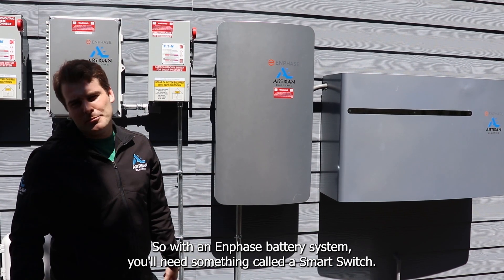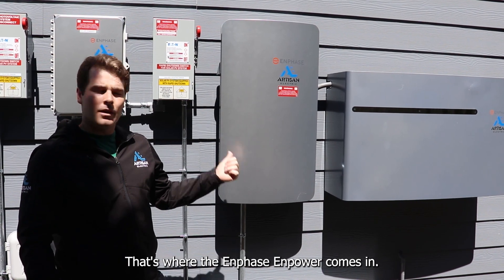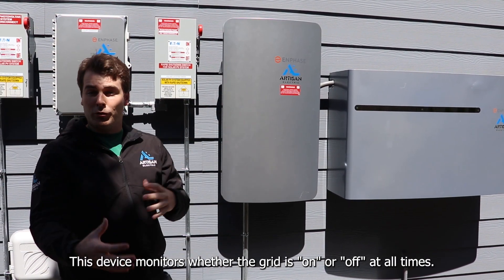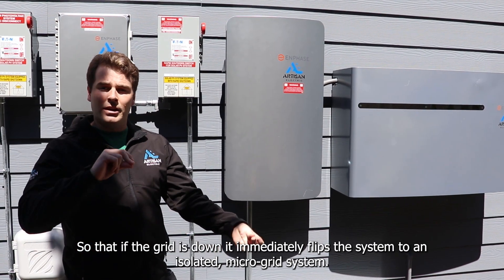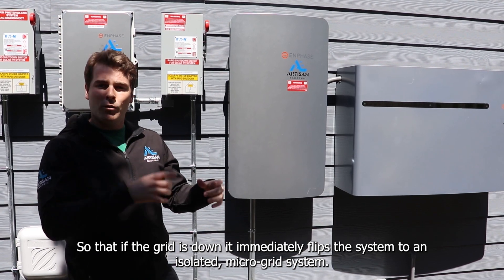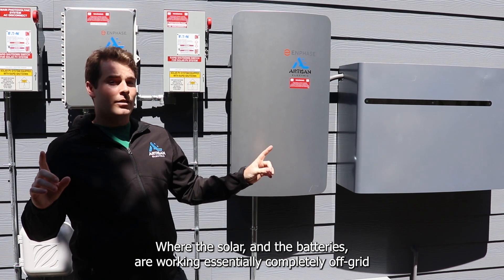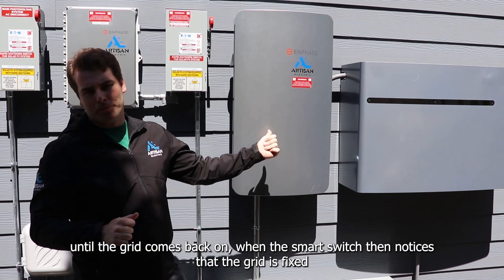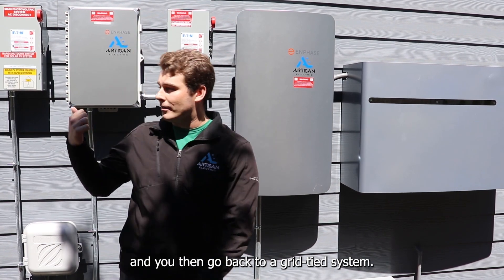With an Enphase battery system you'll need something called the smart switch — that's where the Enphase Enpower comes in. This device monitors whether the grid is on or off at all times, so that if the grid is down it immediately flips the system to an isolated microgrid system where the solar and the batteries are working essentially completely off-grid, until the grid comes back on where the smart switch notices the grid is fixed and you go back to a grid-tied system.